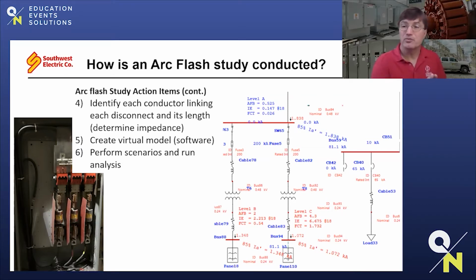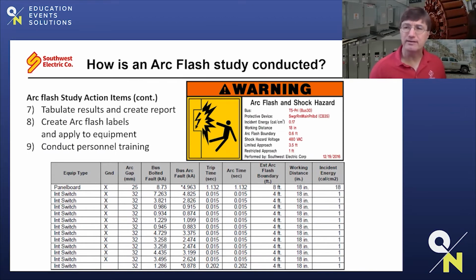When that arc event occurs, we then measure or calculate the response throughout the system, how long that arc may last based on the protection settings, the severity of that arc event, and so on. Based on all these scenarios and all this documented analysis, we can determine the worst case energy levels for each electrical bus throughout your system. Once all those scenarios are run and all that information is determined, this gives us an idea of what risks a facility may face during an arc event. Once we have all those scenarios and all that data and analysis calculated in our software, then a report is generated and it tabulates all these results in a fairly easy to read format that we're going to go over in just a few minutes.